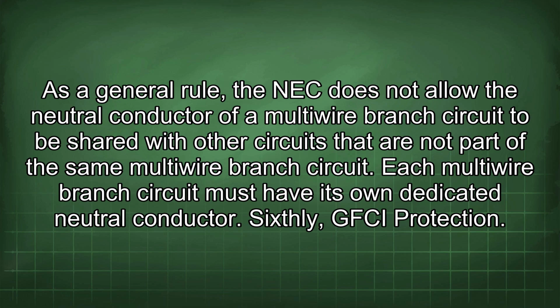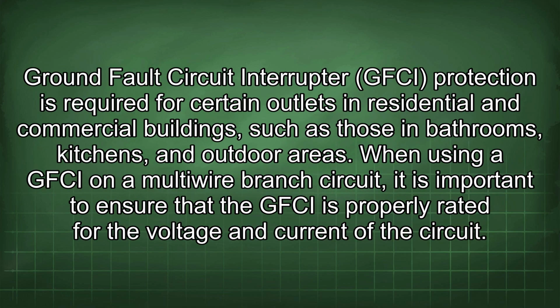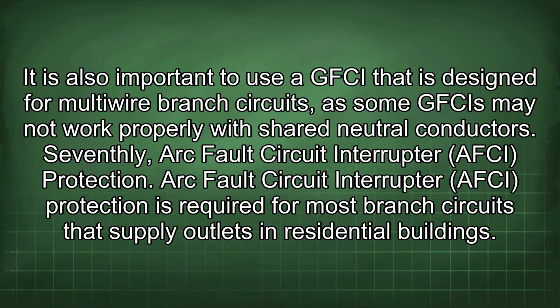Sixthly, GFCI protection. Ground fault circuit interrupter (GFCI) protection is required for certain outlets in residential and commercial buildings, such as those in bathrooms, kitchens, and outdoor areas. When using a GFCI on a multi-wire branch circuit, it is important to ensure that the GFCI is properly rated for the voltage and current of the circuit. It is also important to use a GFCI that is designed for multi-wire branch circuits, as some GFCIs may not work properly with shared neutral conductors.